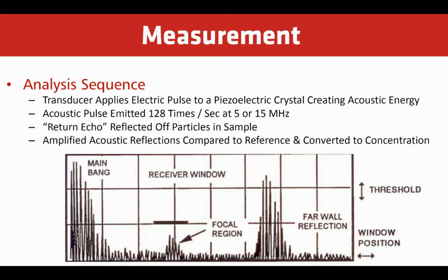We offer these again at either 5 megahertz or 15 megahertz. A 5 megahertz is for higher range, from anything from 2,000 or 2,500 ppm up to about 1 or 2%, depending on sample and actual application. Or we can offer, for low range detection of 0 to about 2,500 ppm with very high sensitivity, a 15 megahertz tip.